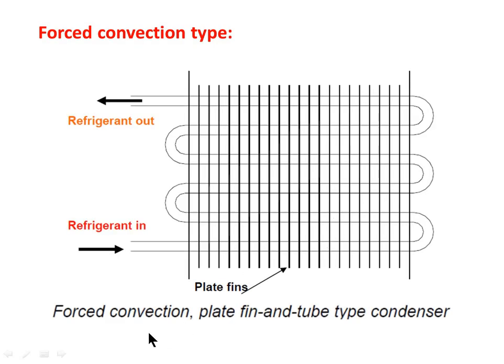Next is the forced convection type of condenser, known as the plate fin and tube type. The plate fins are provided in between the tubes. This is the refrigerant inlet and this is the refrigerant outlet. Refrigerant flows through the tubes, which are embedded in between the plate fins. A fan is provided to enhance the movement of air, which is why it is called a forced convection type condenser.